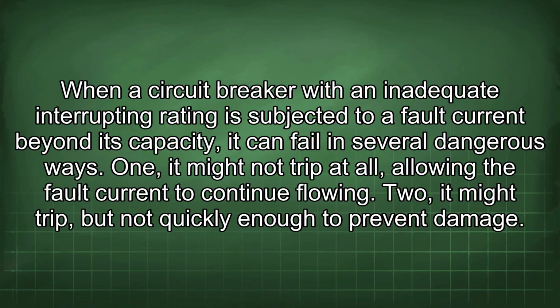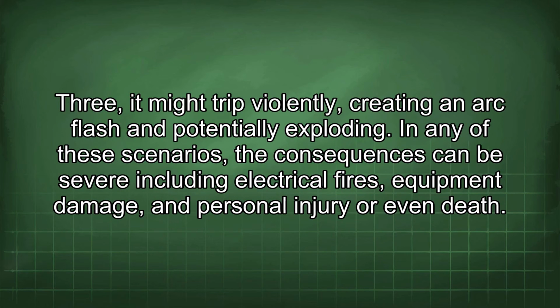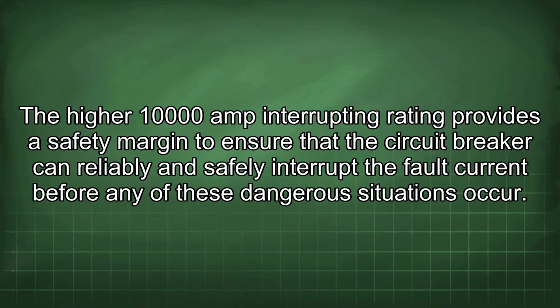When a circuit breaker with an inadequate interrupting rating is subjected to a fault current beyond its capacity, it can fail in several dangerous ways. 1. It might not trip at all, allowing the fault current to continue flowing. 2. It might trip, but not quickly enough to prevent damage. 3. It might trip violently, creating an arc flash and potentially exploding. In any of these scenarios, the consequences can be severe, including electrical fires, equipment damage, and personal injury or even death. The higher 10,000 amp interrupting rating provides a safety margin to ensure that the circuit breaker can reliably and safely interrupt the fault current before any of these dangerous situations occur.